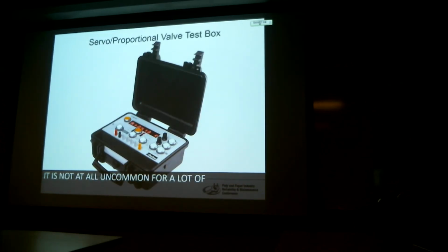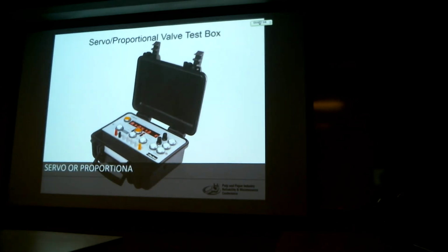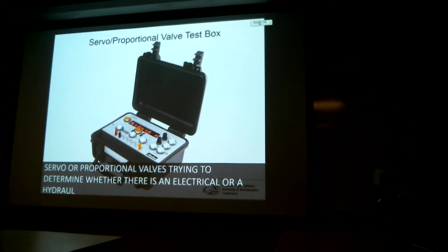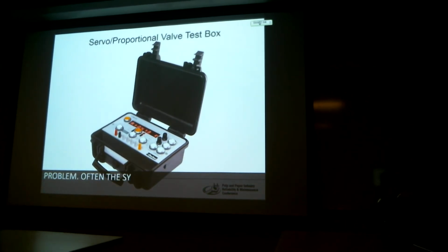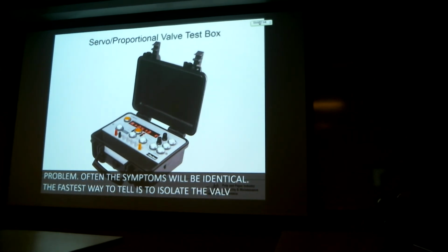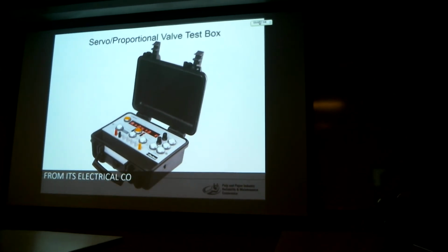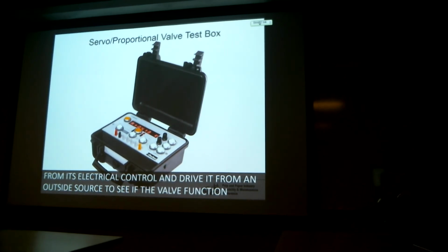It's not at all uncommon for a lot of troubleshooting time to be spent on servo or proportional valves trying to determine whether there is an electrical or a hydraulic problem. Often the symptoms will be identical. The fastest way to tell is to isolate the valve from its electrical control and drive it from an outside source to see if the valve function changes.